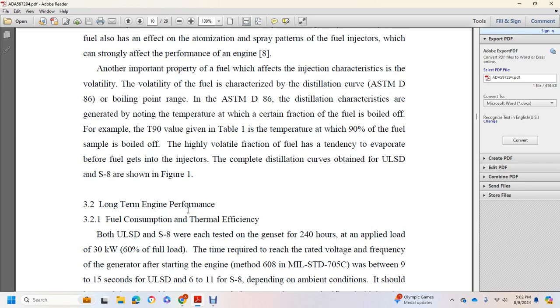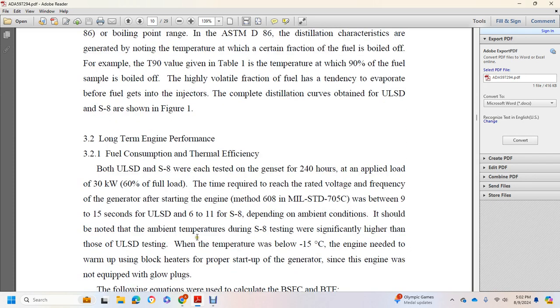3.2, long-term engine performance. 3.2.1, fuel consumption and thermal efficiency. Both ultra-low sulfur diesel and S8 were tested with the generator set for 240 hours, at an applied load of 30 kilowatts, or 60% load. The time required for the generator to reach rated voltage and frequency after starting the engine, by Method 608 of Military Standard 705C, was between 9 and 15 seconds for the ultra-low sulfur diesel and 6 to 11 seconds for the S8, depending on the ambient conditions. It should be noted that the ambient temperatures during the S8 testing were significantly higher than during the ultra-low sulfur diesel testing. The temperature was below negative 15 degrees Celsius, so the engine needed to be warmed up using block heaters for proper startup of the generator, since the engine was not equipped with glow plugs.